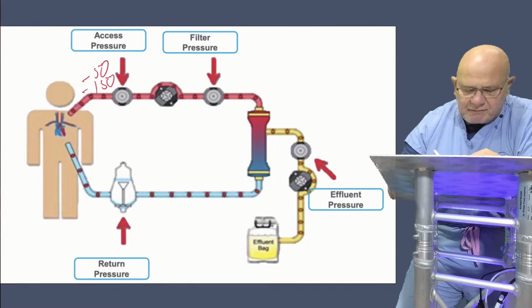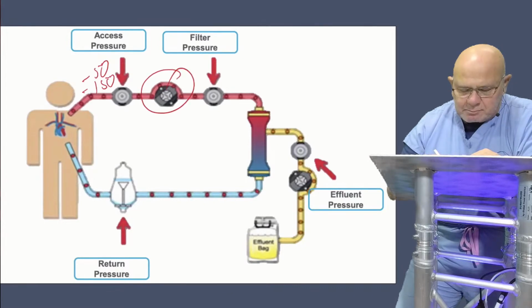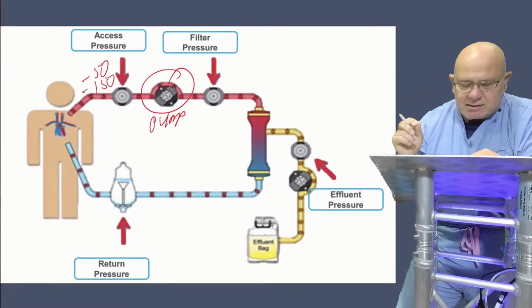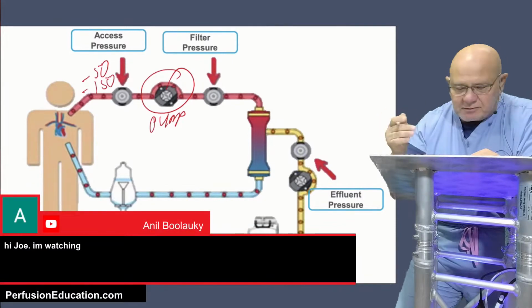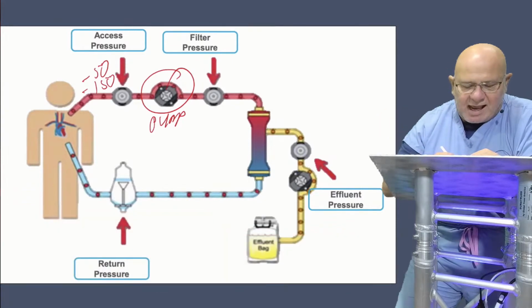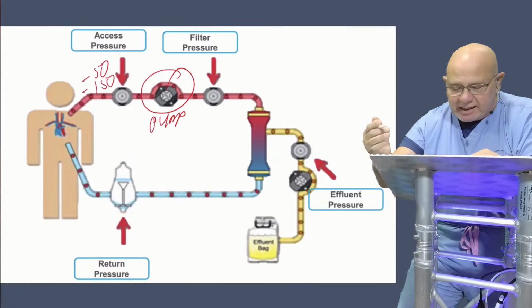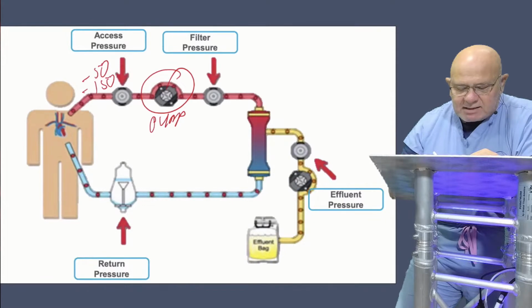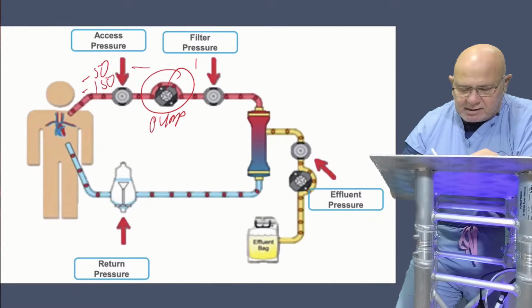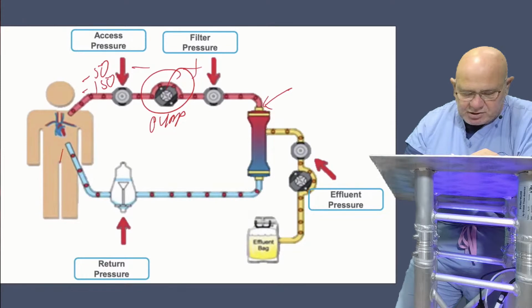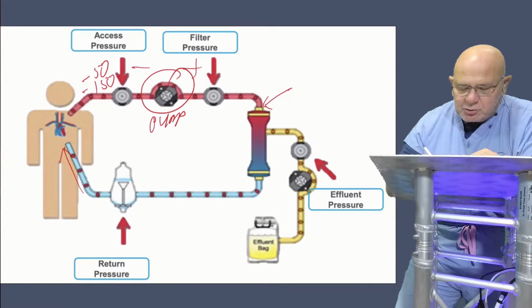It's going to depend on how fast this roller pump, this pump is turning. So the faster your flow, given the same size, and the viscosity of the blood and all those factors are going to influence the access pressure to be more negative. Once you get on the positive side, so this is the negative side of the pump head, this is the positive side of the pump head, right? You're going to have the resistance through the filter here and the resistance going back into the patient here, and all of that is going to be reflected back to the filter pressure.